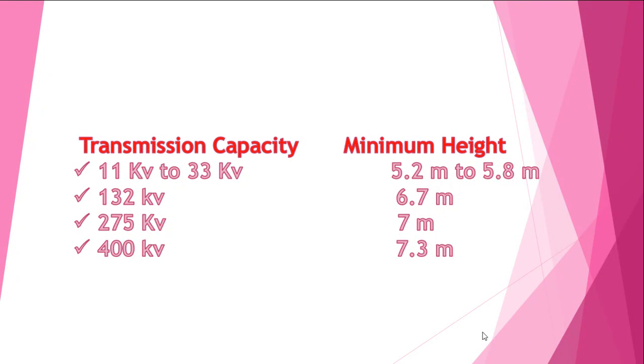If the transmission capacity of overhead power lines is 11 kV to 33 kV, the height is a minimum of 5.2 meters to 5.8 meters. If the transmission capacity is 132 kV, then the height will be 6.7 meters. If the transmission capacity is 275 kV, then the height will be 7 meters minimum. If the transmission capacity is 400 kV, then the minimum height is 7.3 meters.